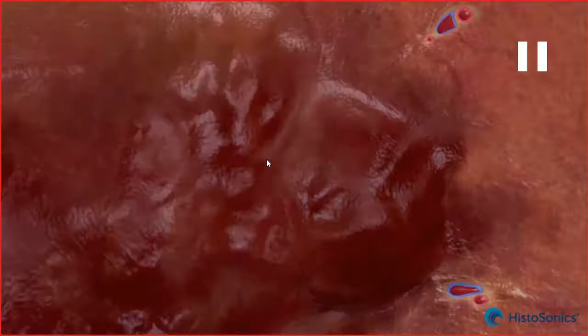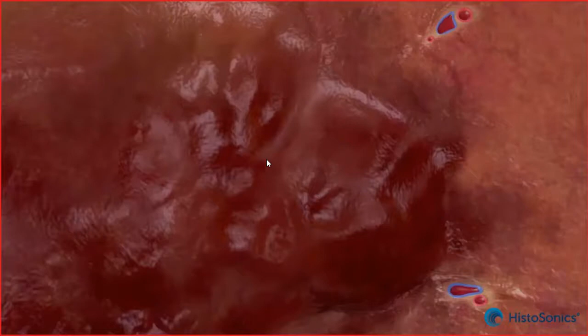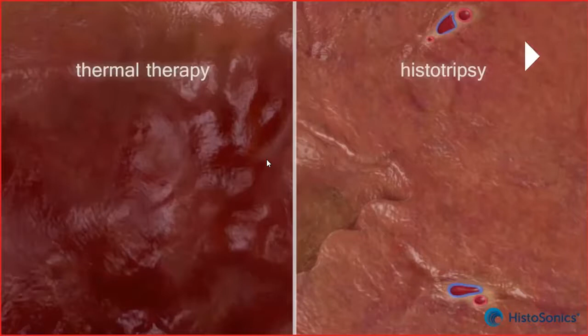So it could also injure and influence other surrounding areas a little bit. And although it is non-invasive and focal, it can have that transition and peripheral zone between the central zone and the surrounding normal tissue. But if we use this cavitation kind of probe, then we can destroy the tissue without having that thermal effect, which has better results and can have fantastic results in comparison to the thermal effect, and the tissue can regenerate and heal itself.